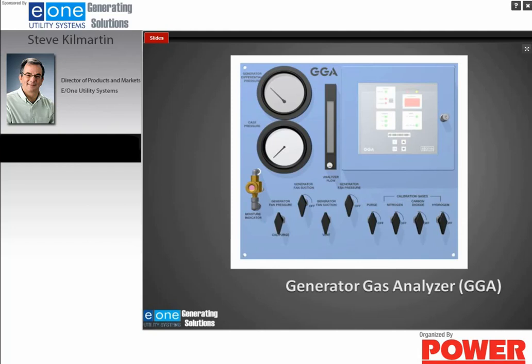This is a picture of a typical generator gas analyzer panel or a hydrogen purity panel. You can see it has the generator fan differential pressure gauge. It has a case pressure gauge. In the lower left-hand corner is a moisture indicator. That's coming from a filter, and that filter is used to keep moisture and oil from getting into the analyzer.